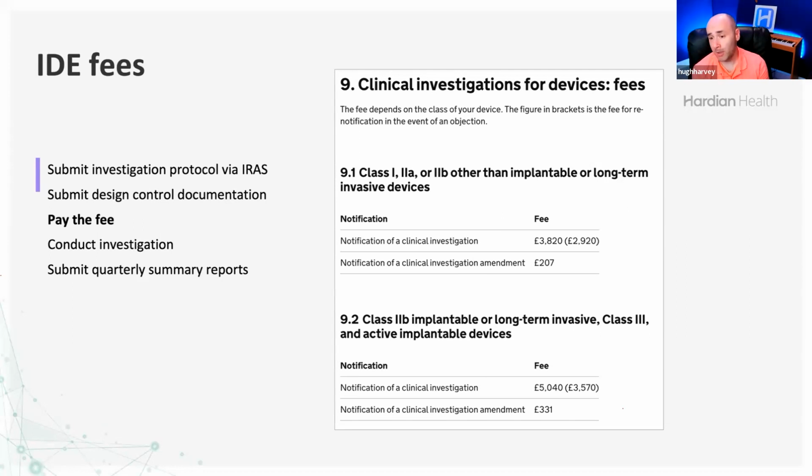I used to work at a company which had a class 1 software device, and the regulators did knock on the door and said, can we see your technical and clinical file? And we did not have one, and we got in trouble. So you can get in trouble from the regulators. So I do not advise you not to do it just because you're a class 1 device. Do not see class 1 as the easy way out. There is still work to be done.